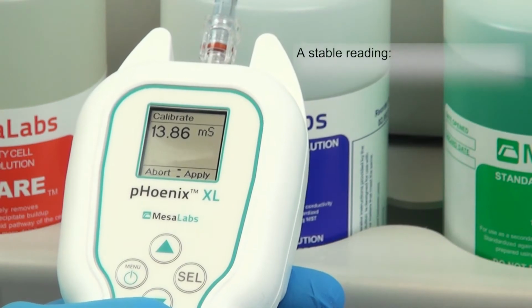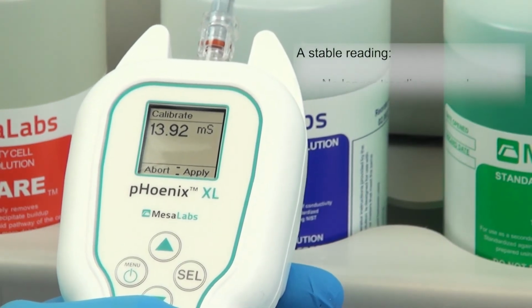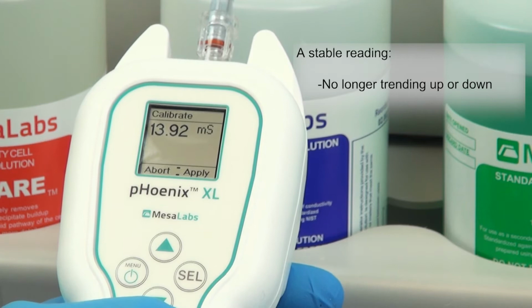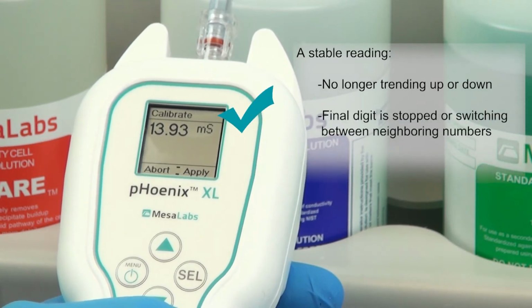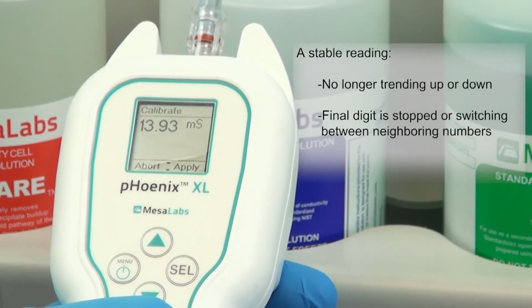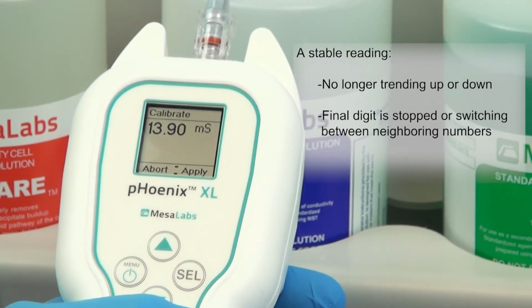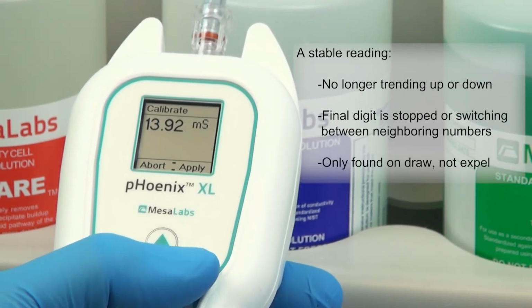Before you start a calibration, remember that when you're in calibration mode, you're not necessarily looking for the right answer or the exact number you see on your standard solution bottle. What you are really looking for is a consistent, stable reading. A stable reading is identified as a reading that is no longer trending up or down, and the final digit of the reading has either stopped or is switching between neighboring numbers. Stable readings can only be identified when pulling the solution into the meter or stopped, not while you are expelling solution.